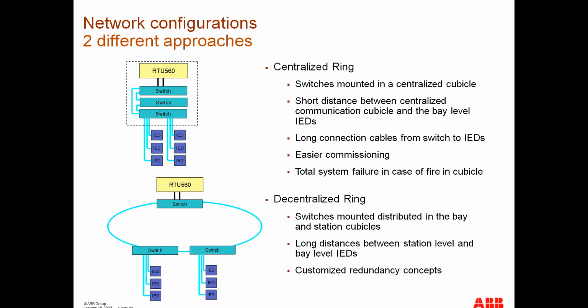And the disadvantage is, of course, if there's a failure, or let's say in the worst case, a total system failure in case of fire or whatever, then your whole system breaks down, because all the intelligence, let's say, of the RTU and the switches and the connections are dead. This won't happen in the decentralized ring. But of course, there are then longer distances between the station level and the bay level IEDs, and it depends on the customer requirements which solution is the best. It is always a question of the customer ideas.